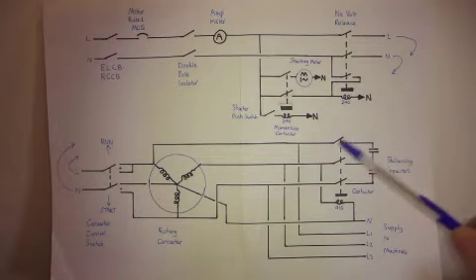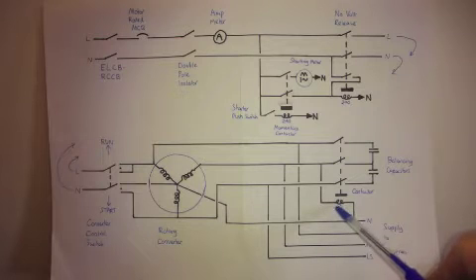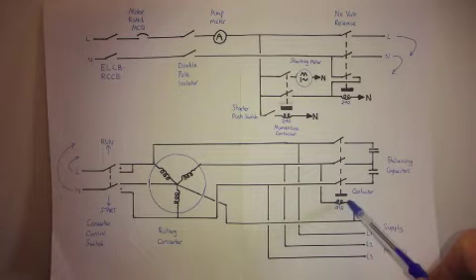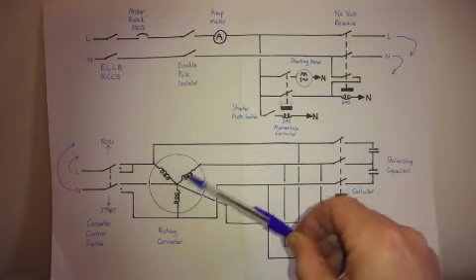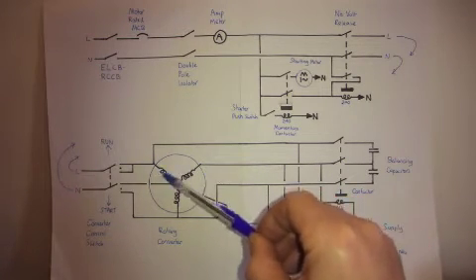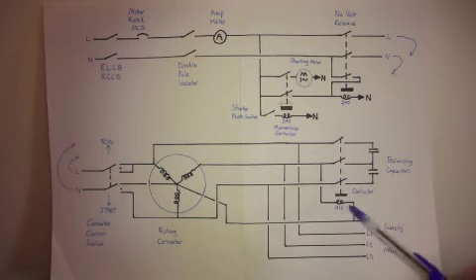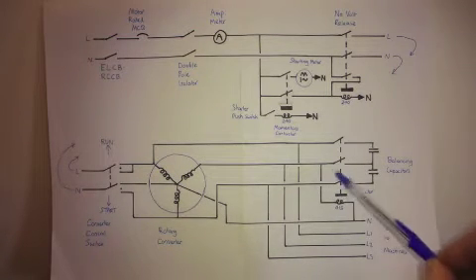So I've overcome this by wiring the contactor coil. This is a bit of a bodge but it does work. I've bought a 415 volt coiled contactor that runs off one of the false phases. It's important that it comes off one of the false phases and not the true live here, which goes back to the star point. That's really only truly getting 240.